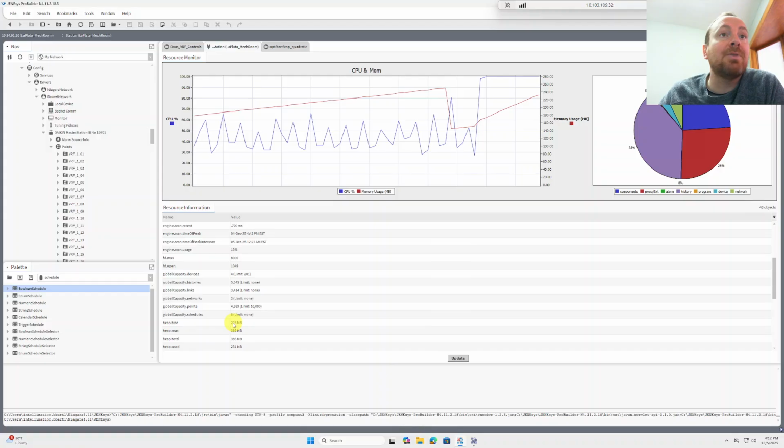So it's got plenty of memory on this JACE, and our CPU usage is really high. I just noticed that now. Maybe that's just because we did a compile or something, but our CPU usage should be consistently below 80%, which it looks like it was. I might have been doing something here to cause that, but it's important to watch for that too.